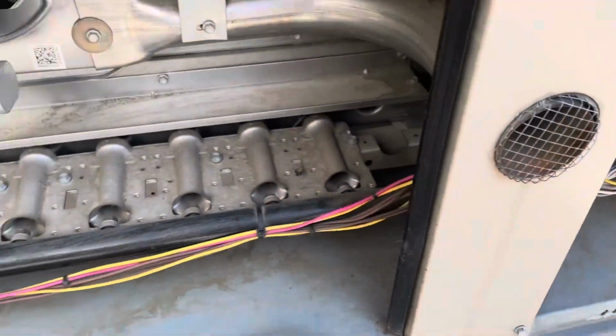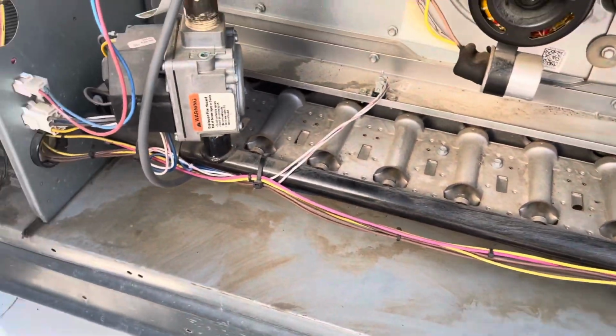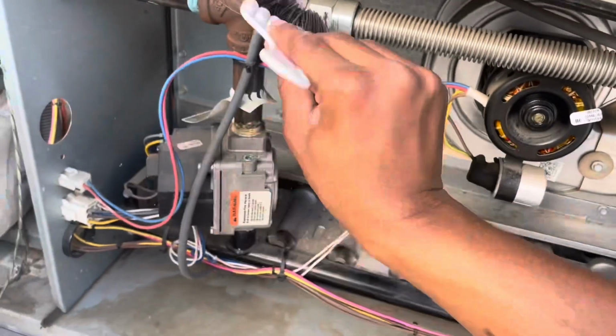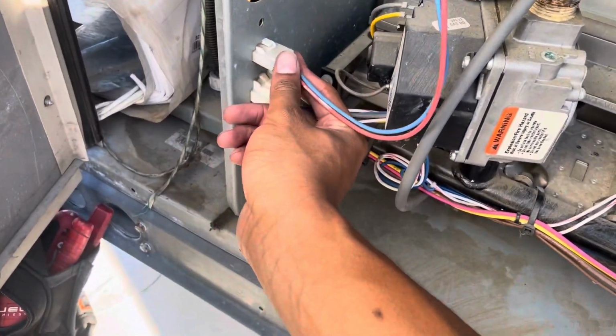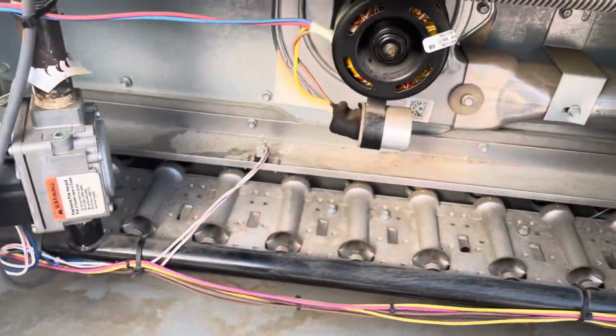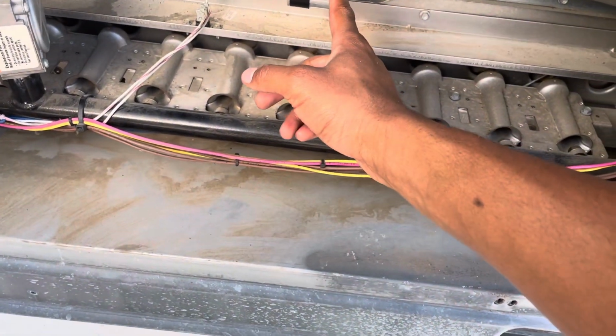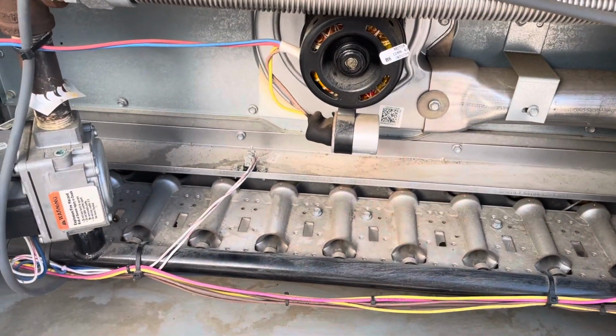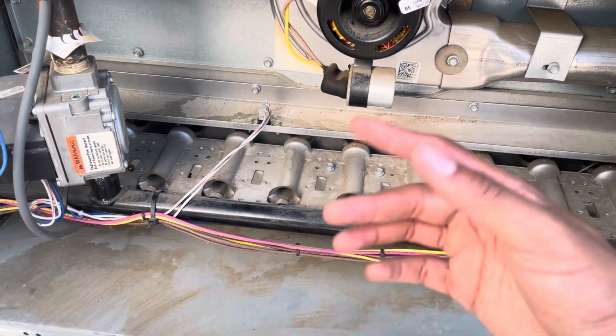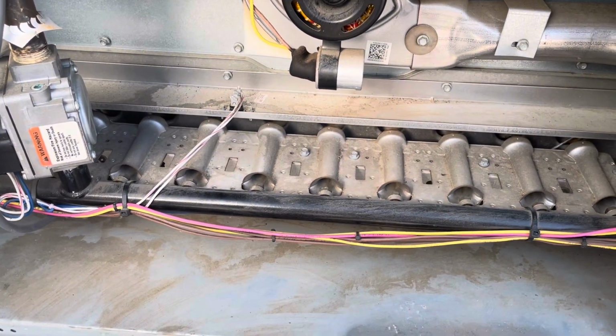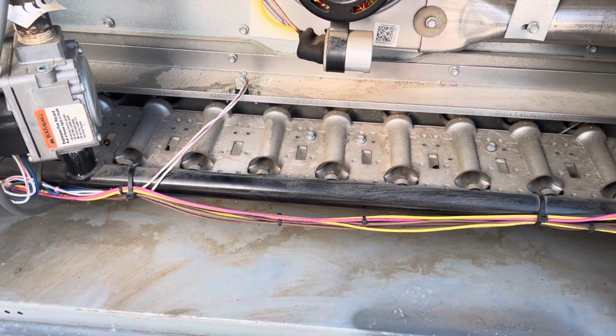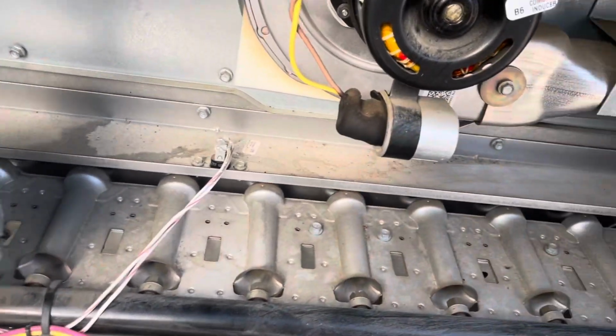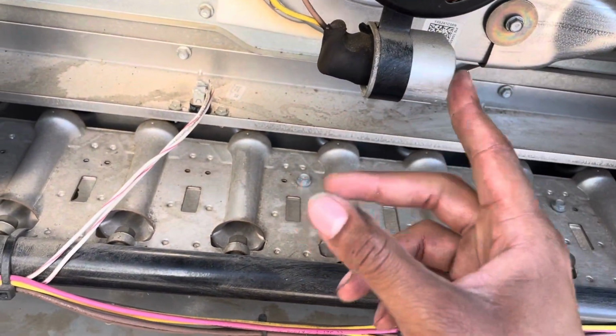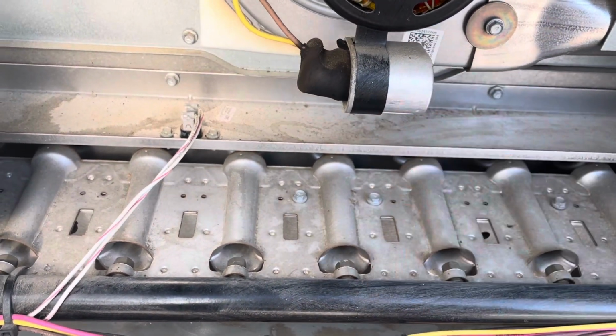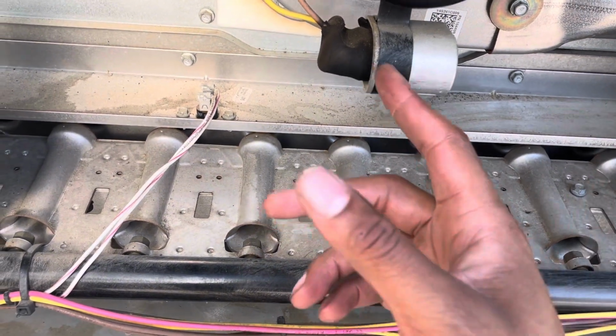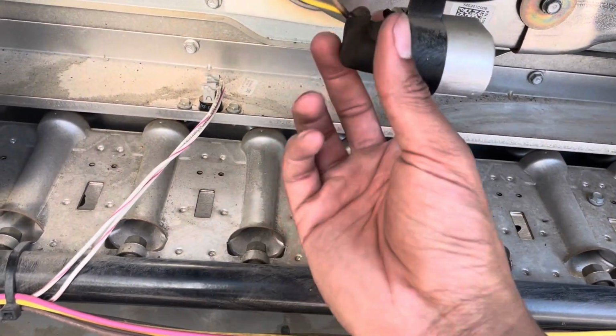All right, so that's one thing you can do. Also, obviously, check all of your wire connections. Make sure everything is nice and tight. Nothing is loose. Take a look at the capacitors, because sometimes they will be super rusted. This is a newer unit, so everything in it is relatively new. But in older units, you may have super rusted capacitors. Those are things that you obviously want to check.